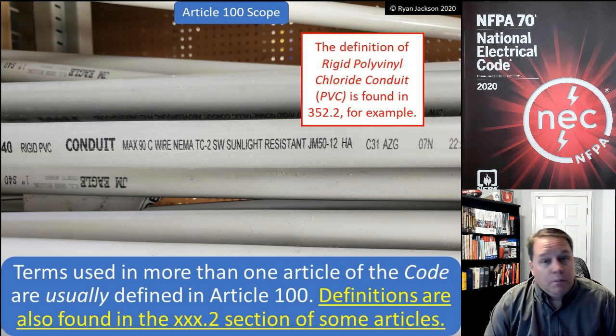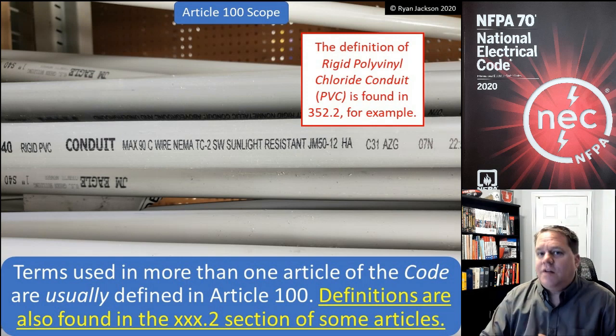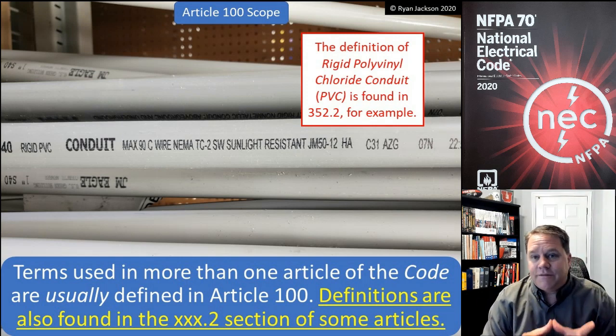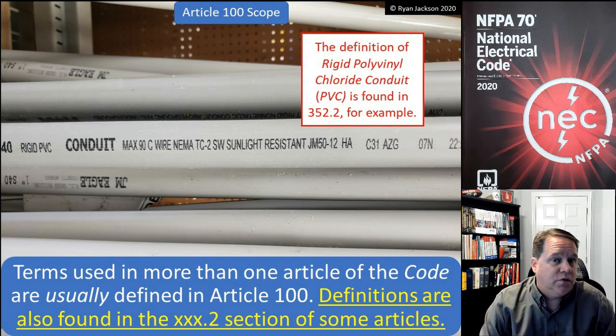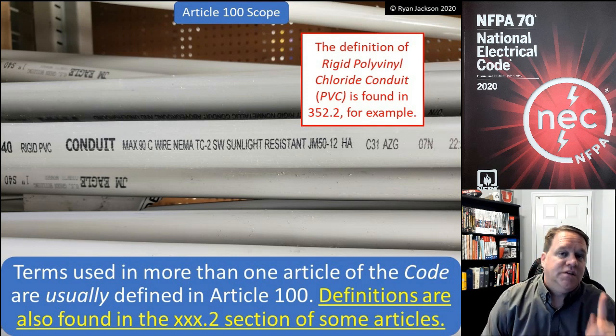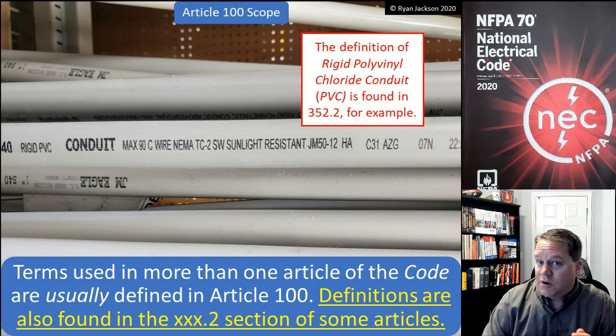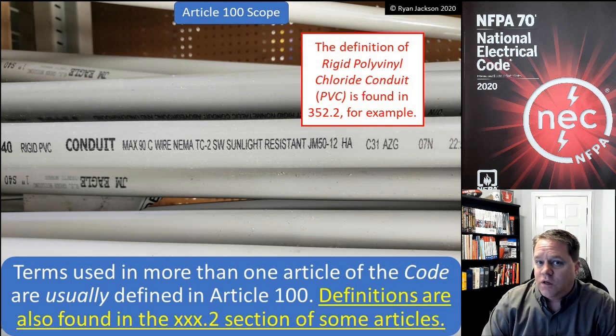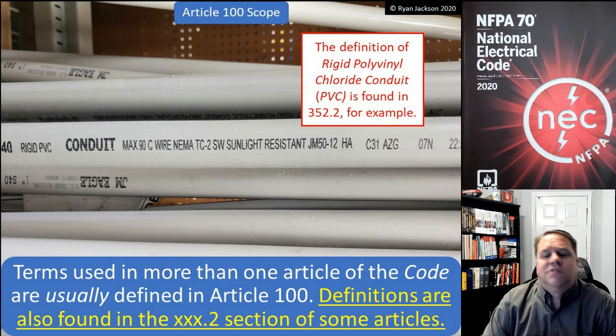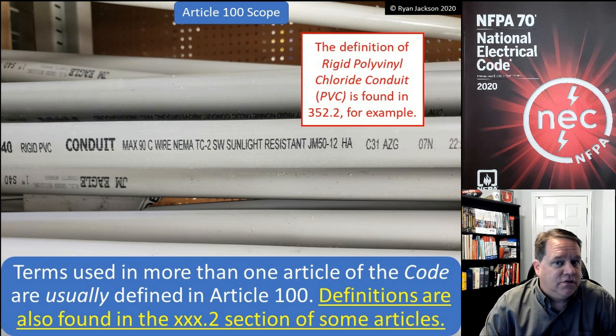Terms used in more than one article of the code are supposed to be defined in Article 100 — that's how Article 100 works. Not every definition in the NEC is found in Article 100; only definitions used in more than one article are found there. At least that's the way it's supposed to work. In the 2020 code they added language — highlighted in yellow — saying that definitions are also found in the .2 sections of some articles.